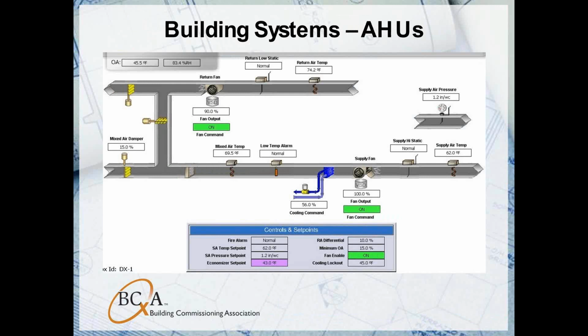It took a while. But one of the comments to make on this plant is that a lot of times the engineer who had designed it said, run the series counterflow machines as your lead because that's the normal, most efficient way to operate. And we concur with that. The struggle is that in part load conditions, this building would run sufficiently with only one of the 400-ton machines in operation, and the second, series counterflow machine would be trying to run because it's enabled, it's calling to run, but the unit would end up basically short cycling out on low temperature because the load wasn't there to sustain it. And that's what Mark was talking about, false loading.